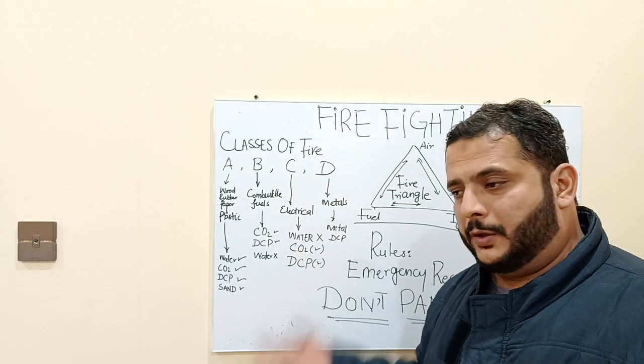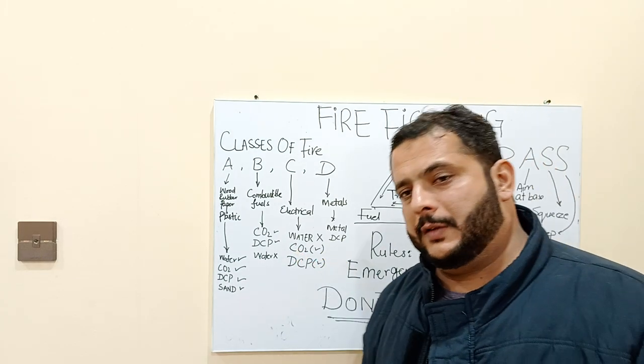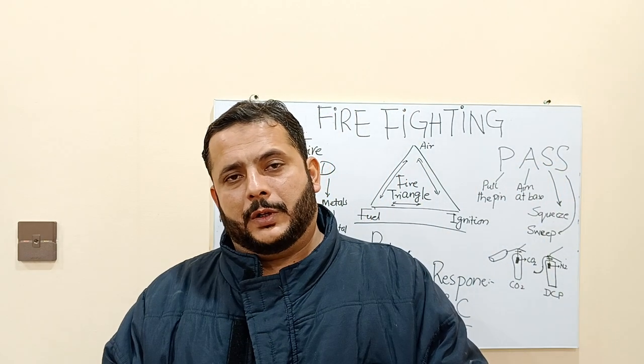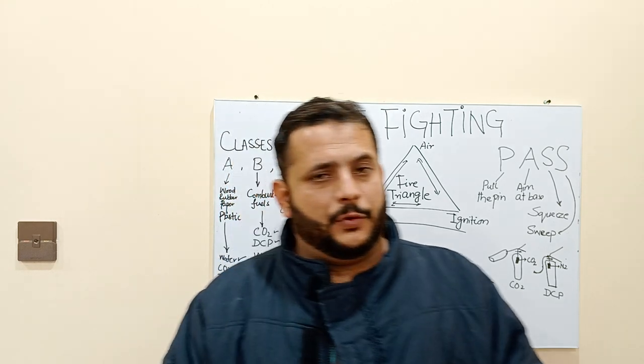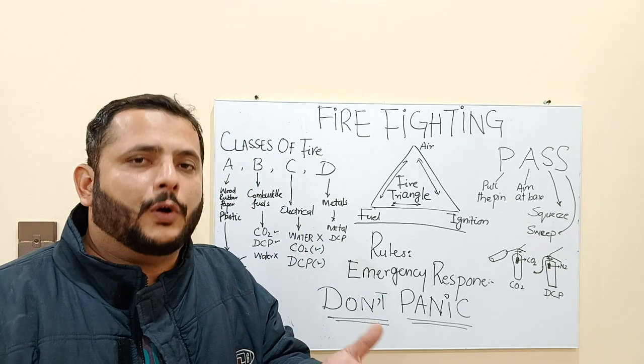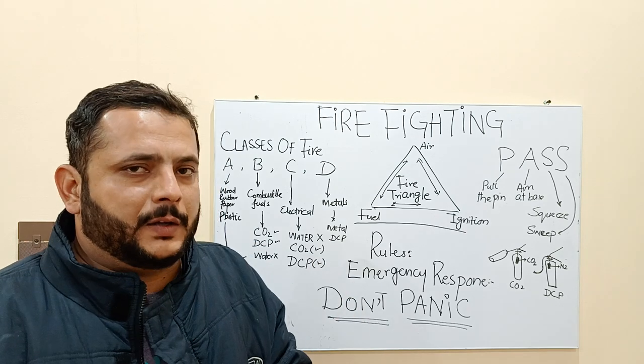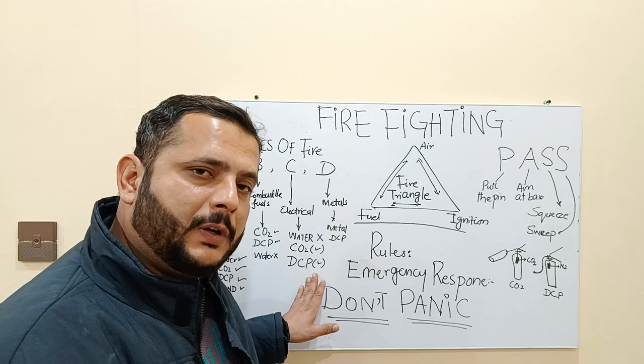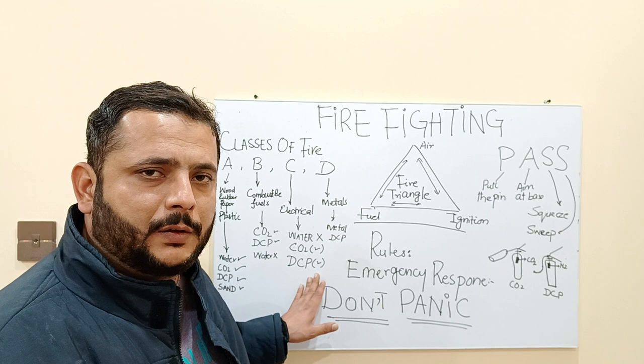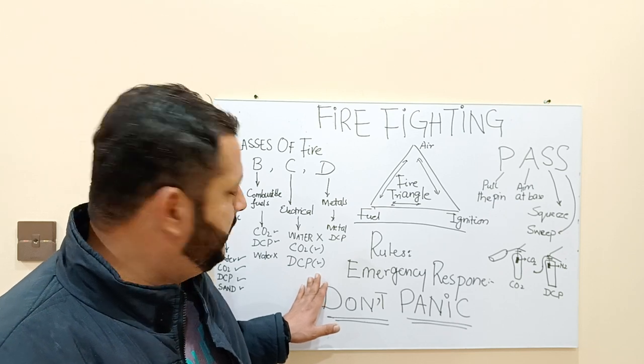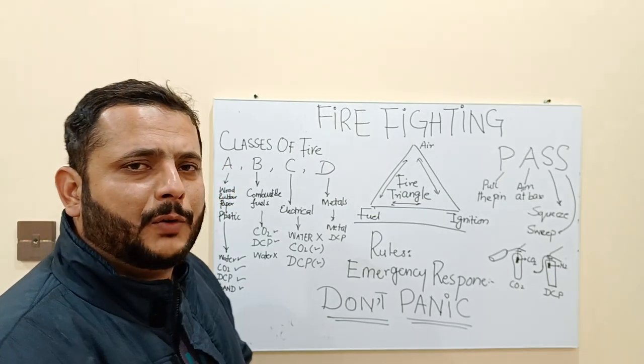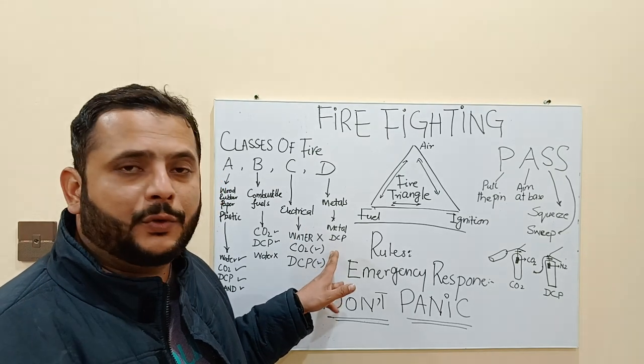CO2 is prioritized for electrical fires because when electrical equipment is damaged, you can use CO2 to extinguish the fire and the gas dissipates from the equipment after some time. If you use DCP on electrical equipment, the dry chemical powder inside will coat the electrical devices. Since DCP is a powder it leaves a residue on the equipment, whereas CO2 being a gas removes itself after some time. That is why CO2 is the priority for electrical fires.